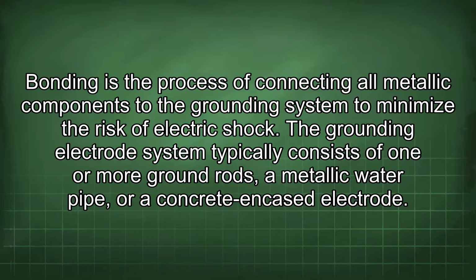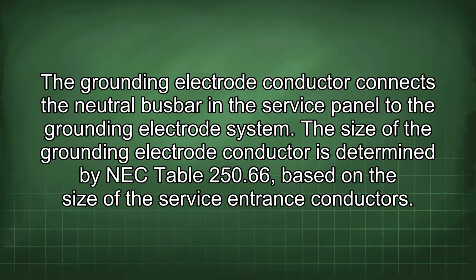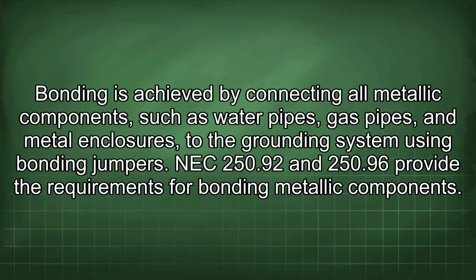encased electrode. The grounding electrode conductor connects the neutral busbar in the service panel to the grounding electrode system. The size of the grounding electrode conductor is determined by NEC Table 250.66 based on the size of the service entrance conductors. Bonding is achieved by connecting all metallic components such as water pipes, gas pipes, and metal enclosures to the grounded system using bonding jumpers. NEC 250.92 and 250.96 provide the requirements for bonding metallic components.